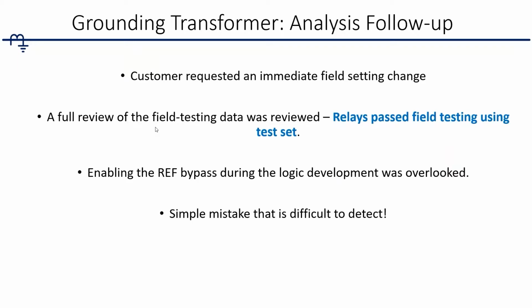So a follow-up from this was we went back to the customer and talked to them a little bit about what our findings were and what our recommendations were. We went in and changed the REF bypass to turn it on. And the customer requested an immediate field change. So we went out, made the settings changes, and moved on from there. They also wanted a full review of other relays in the field. So they wanted us to go back and dig in and make sure there were no other surprises that were going to come up, because this is exactly what we were looking for.